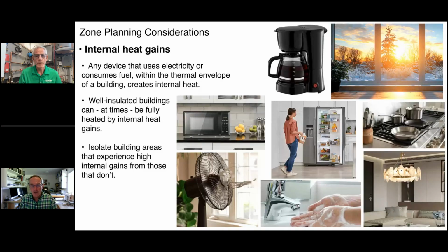And these internal heat gains can vary certainly from one room to another, based on solar exposure and based on the appliances or the equipment that are in those rooms. So when you have the potential for widely varying internal heat gains, those are good spaces to consider on separate zones. And it could even be room by room zoning to allow each room to independently adjust the heat output from the hydronic system based on what is happening with internal heat gains.